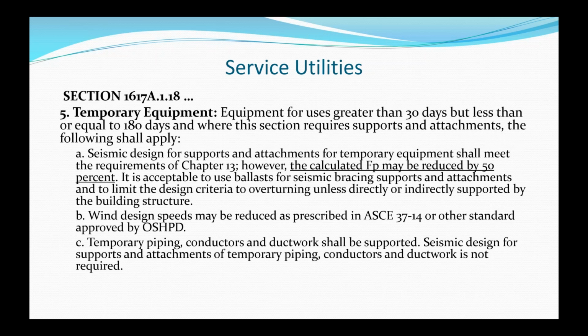Equipment for use greater than 30 days, but less than or equal to 180 days. And where this section requires supports and attachments, the following shall apply. This is kind of the basis. This is actually in section 1617A of the building code. But basically it states that seismic design for the supports and attachments for temporary equipment shall meet the requirements of chapter 13, except we're allowing a 50% reduction in the F sub P calculations. So only half the requirement is required. It is also acceptable to use ballast for the seismic bracing supports and attachments to limit the design criteria to overturning unless directly or indirectly supported by the building structure.